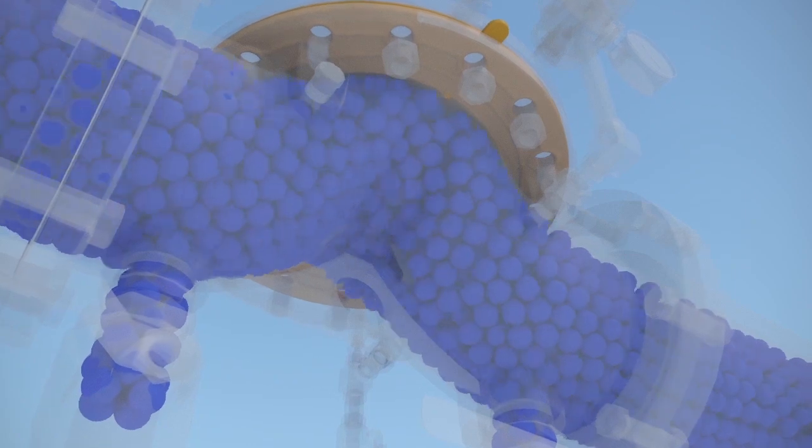In this way, the water supply pressure in the inlet chamber forces the diaphragm off from the valve seat, therefore allowing the water present in the main pipe to flow towards the discharge nozzles.